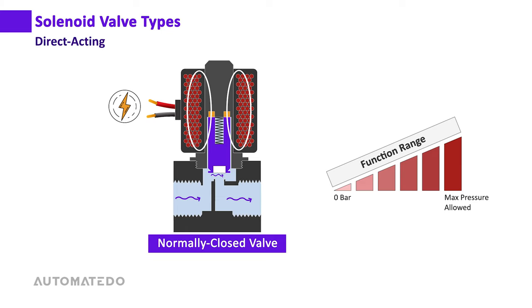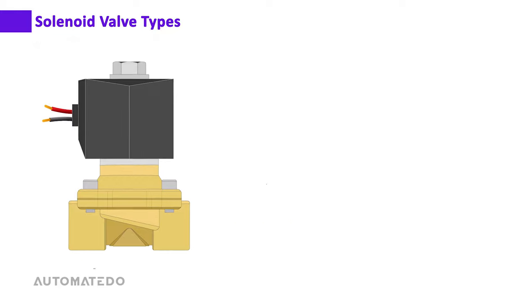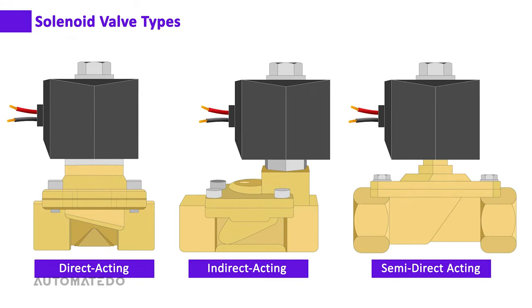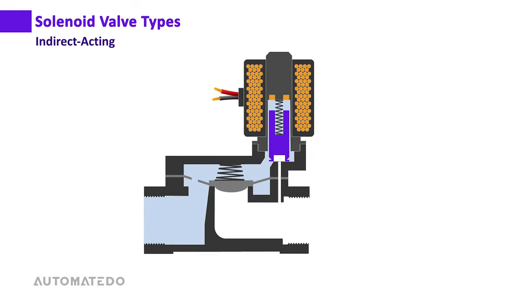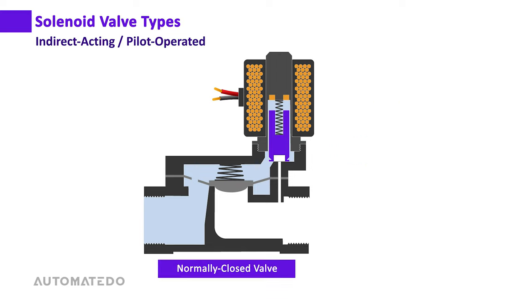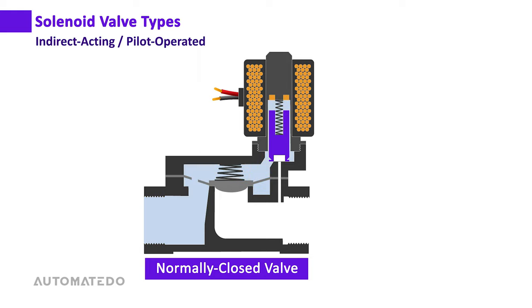Now let's look at the indirect acting solenoid valve, also known as a servo or pilot operated solenoid valve. Its main components are the coil winding, armature, spring, plunger, valve body, pilot orifice, and diaphragm. Consider a normally closed valve: two chambers are separated by a diaphragm, and there is a pinhole in the diaphragm.